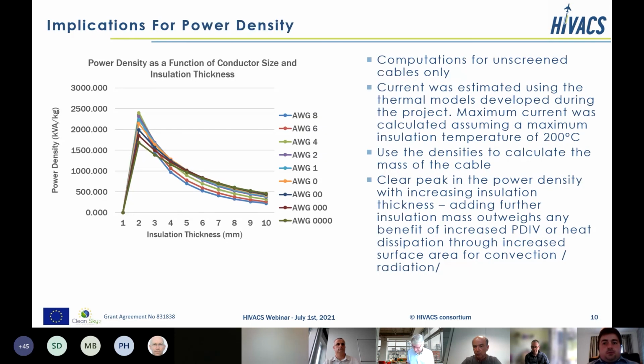So on to some implications for power density. Very simple analysis. We use the PDIV values obtained for unscreened cables, and the current ampacity levels estimated for a maximum operating temperature of 200 degrees C, and calculated the power, and then used the density to estimate the mass of the cable per meter to give sort of indication of the gravimetric power density in kVA per kilogram.